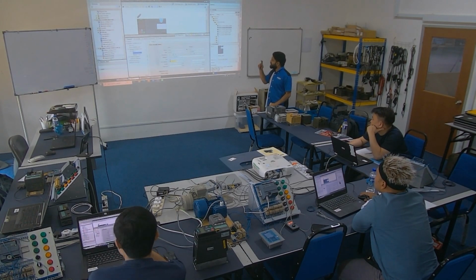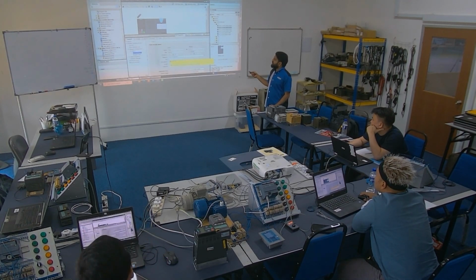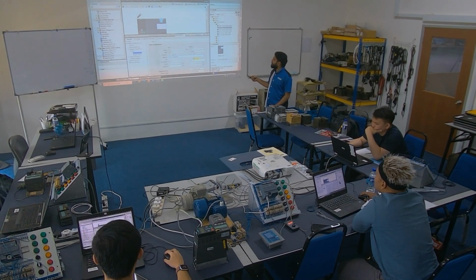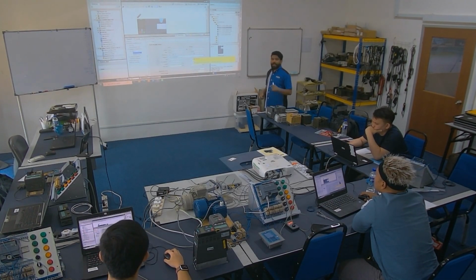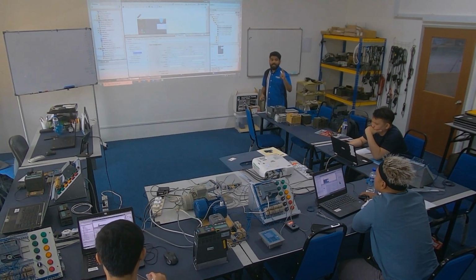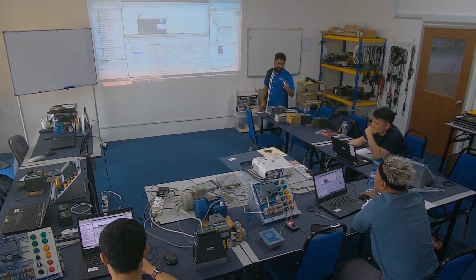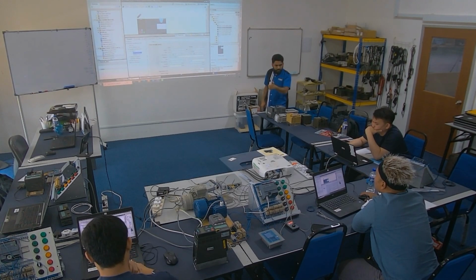Okay, first the drive and the partner is the PLC, right? PLC, yeah. We chose standard Telegram 1 just now. Standard Telegram 1 means it will give you two data. Actually both data are words, 16-bit. Okay, because speed, right? Speed, yeah, the set value. But if you want to control also, same word. Okay, I will tell you how.